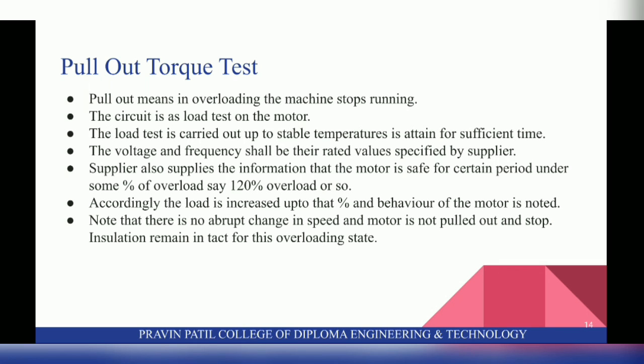Next is pull out torque test. Pull out means overloading, the machine stops running. The circuit is a load test on motor. The load test is carried out up to stable temperature is attained for sufficient time. The voltage and frequency shall be their rated values specified by supplier.